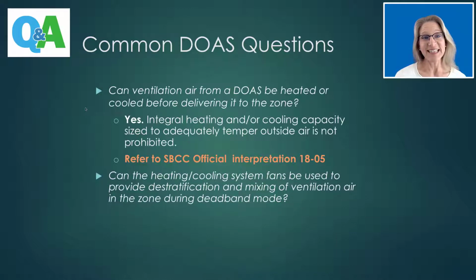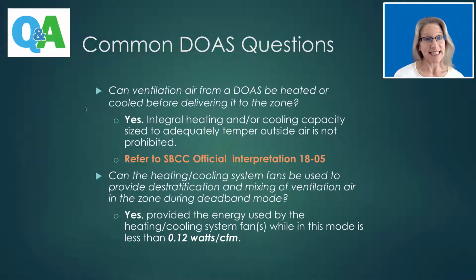Another question we get is, can the heating and cooling system fans be used to provide destratification and mixing of ventilation air within the zone when the heating and cooling system is in deadband mode? And the answer to this is yes. There is an exception to the criteria that the heating and cooling systems must be turned off in deadband mode. You can use those heating and cooling system fans as long as, while in that mode, the fan power required for those fans does not exceed 0.12 watts per CFM.